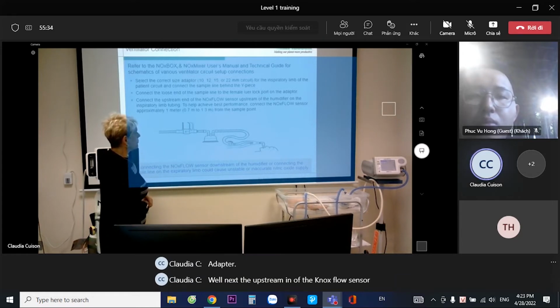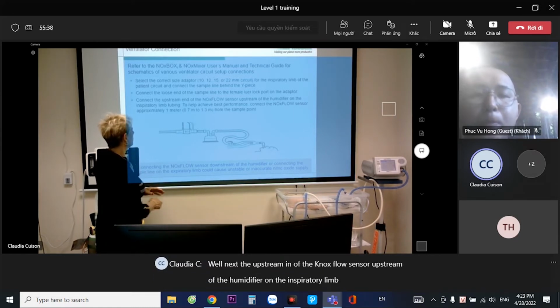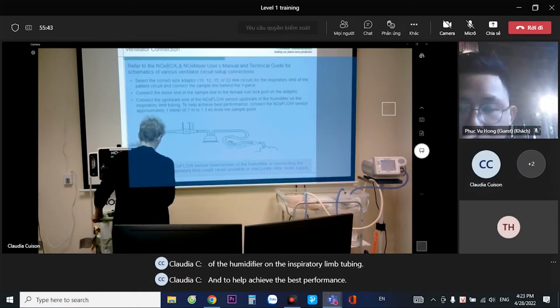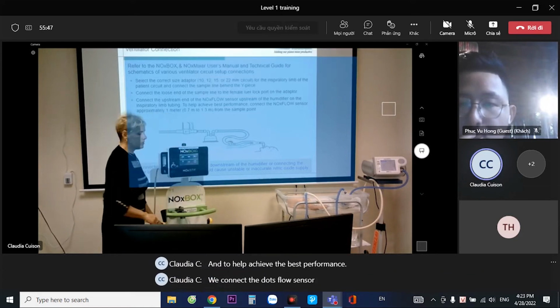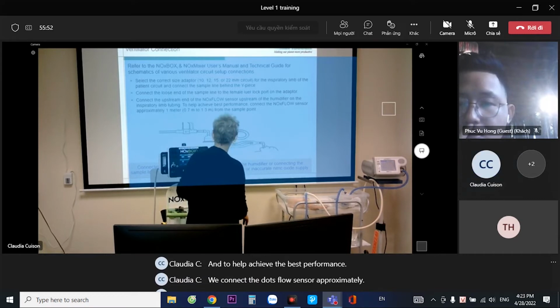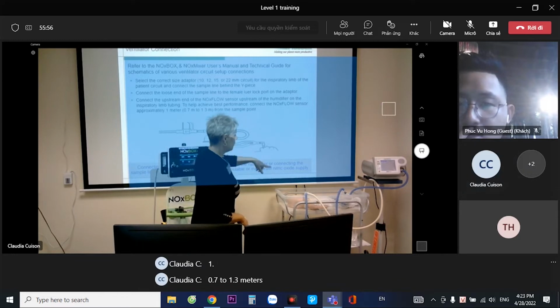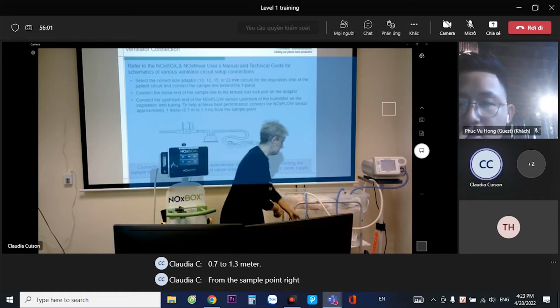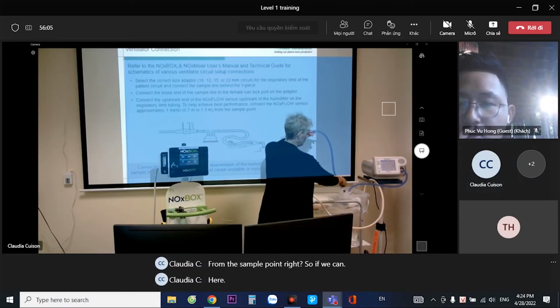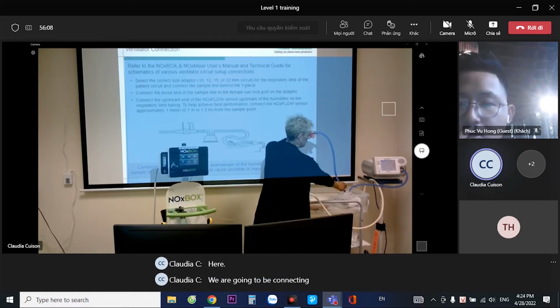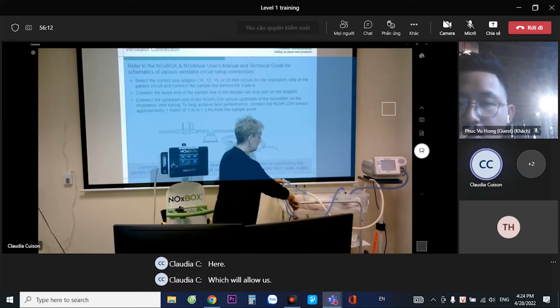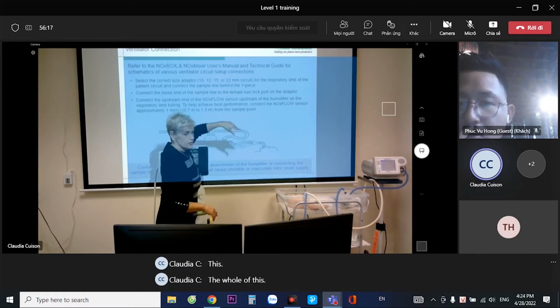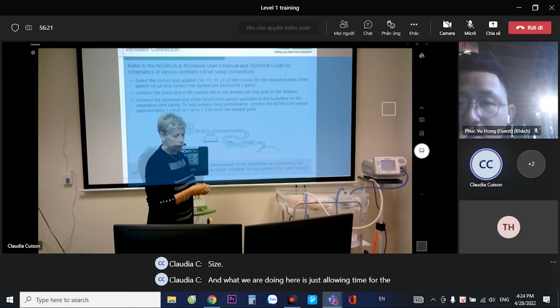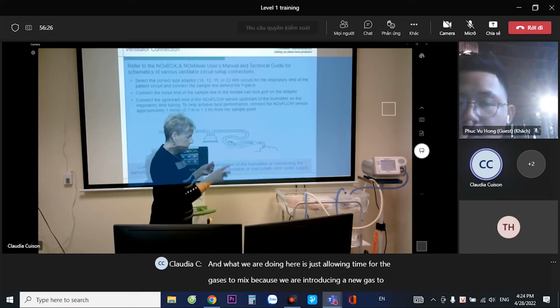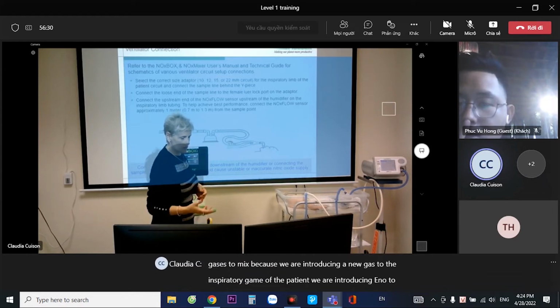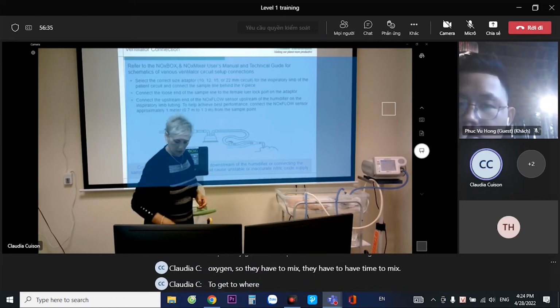Connect the upstream end of the NOx flow sensor upstream of the humidifier on the inspiratory limb tubing. And to help achieve the best performance, we connect the NOx flow sensor approximately 0.7 to 1.3 meter from the sample point, right? So if we can read here, we are going to be connecting here, which will allow us the whole of this size. And what we are doing here is just allowing time for the gases to mix, because we are introducing a new gas to the inspiratory limb of the patient. We are introducing NO to oxygen. So they have to have time to mix to achieve the best, let's say, performance.